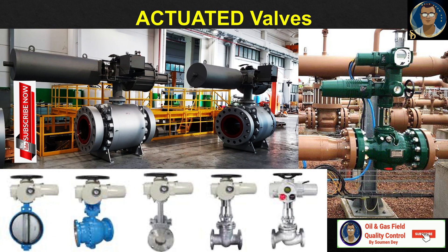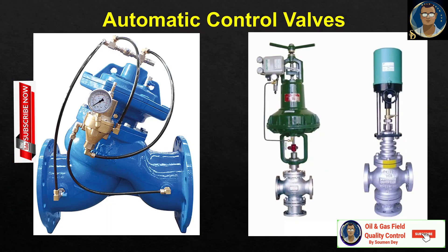Actuated valves are usually connected to electrical motors, air or pneumatic systems, hydraulic systems or solenoids. These valves allow remote control and automation for high accuracy or large scale applications. Automatic valves are those which get activated only when specific flow conditions are met. For instance, check valves closing during back flow, or pressure release valves that get activated when an over-pressure condition is detected.